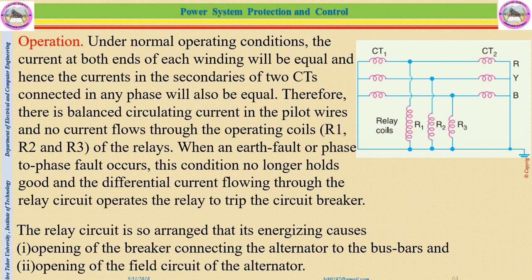When an earth fault or phase-to-phase fault occurs, this condition no longer holds good, and the differential current flows through the relay circuit, operates the relay and trips the circuit breaker. If the fault happens, for example, somewhere around here, this current is much greater than this current. So this current may be approximately zero, and the rest of the current will flow across this line, so the two currents cannot be equal. The CT1 current cannot be equal to the CT2 current. So there is some current which passes through R1.